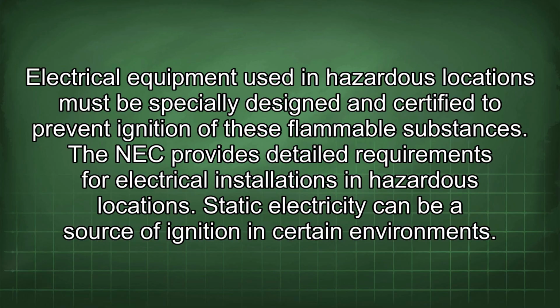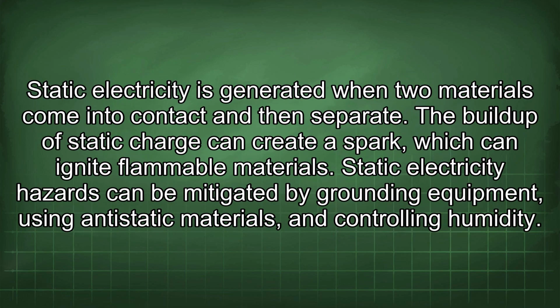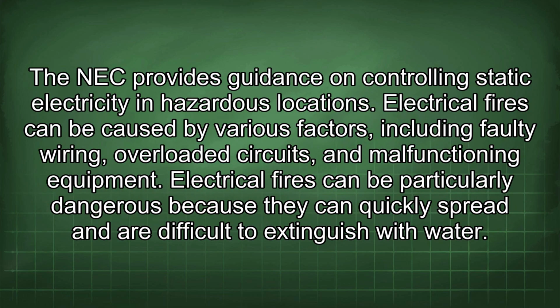Static electricity can be a source of ignition in certain environments. Static electricity is generated when two materials come into contact and then separate. The buildup of static charge can create a spark, which can ignite flammable materials. Static electricity hazards can be mitigated by grounding equipment, using anti-static materials, and controlling humidity. The NEC provides guidance on controlling static electricity in hazardous locations.